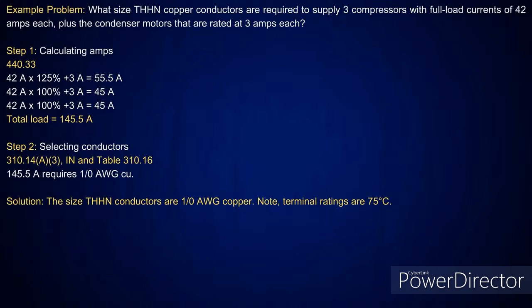Now, this one, like I said, you take the largest motor at 125%, everything else is added at 100. Let's take a look here. I've got three compressors. They're all the same, 42 amps each, and each condenser is rated at 3 amps. So you'll see in 440.33, I took one of the 42 amps at 125%. Everything else was added at 100%. Add all of that up, it gives you 145.5 amps. Go to table 310.16, 75° C column. The next size above that is 150 amps, which requires a 1-aught conductor.